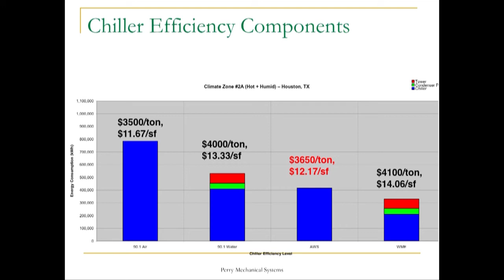So you can see just the chiller is about the same efficiency on the water-cooled versus the air-cooled. The only way to really improve energy-wise over this is to go to some of the newer water-cooled technologies, which are like the magnetic machines. And then you get into a realm over here. But again, you're going to be even more expensive than this one here, because you've got to pay for that additional water-cooled infrastructure plus the additional technology. But you're still looking at a significant improvement, so it definitely makes sense.